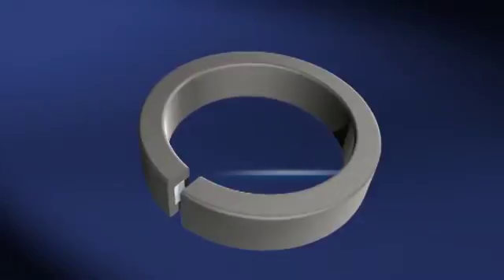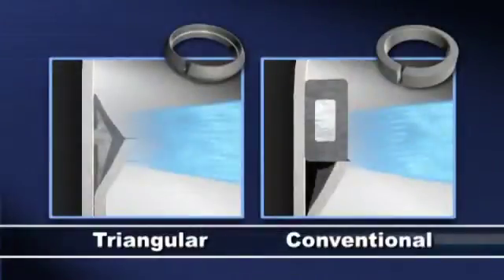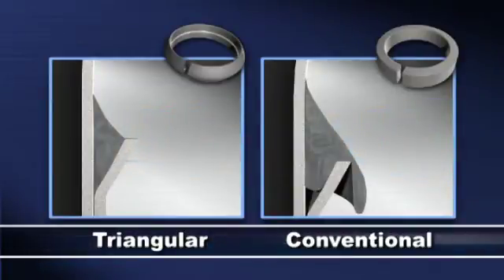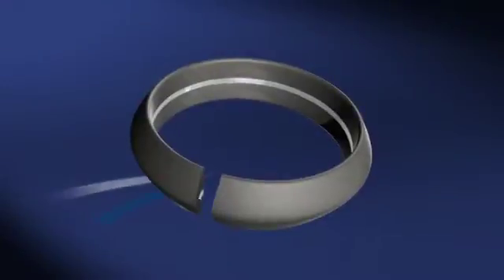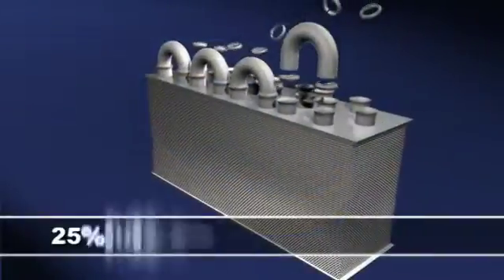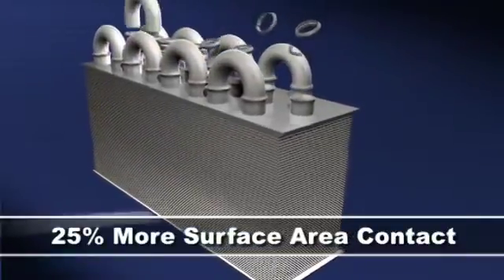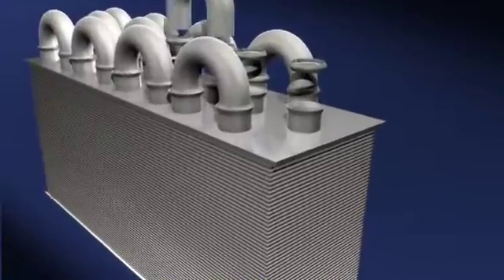Conventional rounded or rectangular aluminum brazing rings do not seat as well and can melt before the flux is activated. This can cause joint overflow and inconsistent joint quality. With our patent-pending triangular cross-section brazing rings, there is 25% more surface area contact between the hairpin and return bend compared to round or rectangular rings.